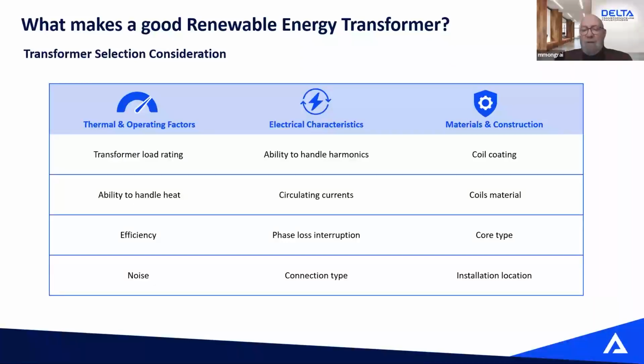You have to have the capability of handling phase loss interruption by how we build the core of the transformer. Connection type, depending on what system I have. Do I have a three-phase 4-wire grid on my building? Does my inverter have a three-phase 4-wire output? So these are all things that need to be taken into consideration. Then you have the coil material. Do I go with copper, aluminum?